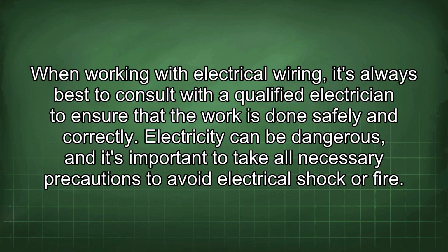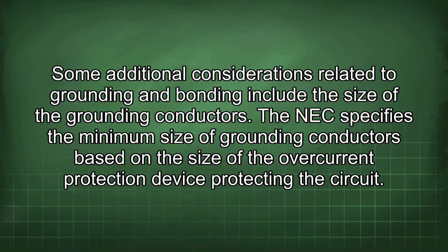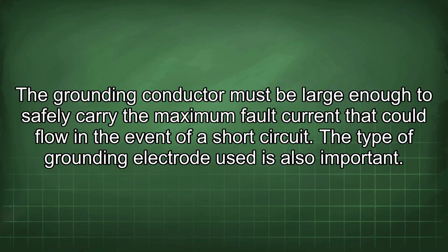shock or fire. Some additional considerations related to grounding and bonding include the size of the grounding conductors. The NEC specifies the minimum size of grounding conductors based on the size of the overcurrent protection device protecting the circuit. The grounding conductor must be large enough to safely carry the maximum fault current that could flow in the event of a short circuit.